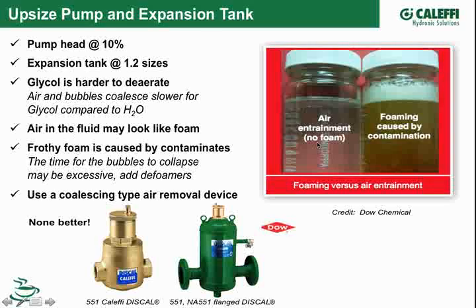So when you're doing an installation, just remember it's going to take longer. If you've never used glycol before, it takes a lot more time to vent all that air out of the system. So don't be fooled thinking, hey, I got it all out. And don't also be fooled thinking you have a foaming problem when really you might just have an air entrainment problem, you just didn't remove all the air from the system. A foaming problem means those bubbles just don't collapse in a reasonable amount of time.